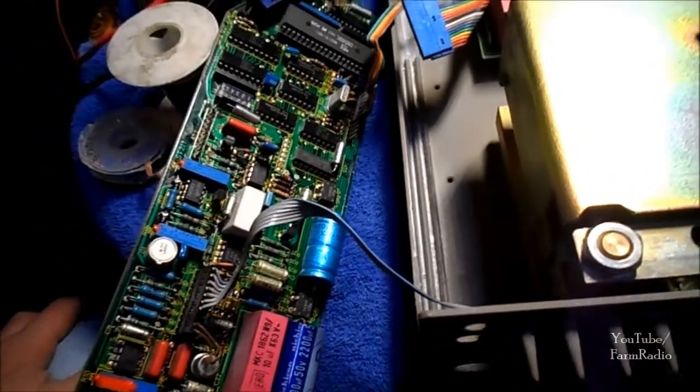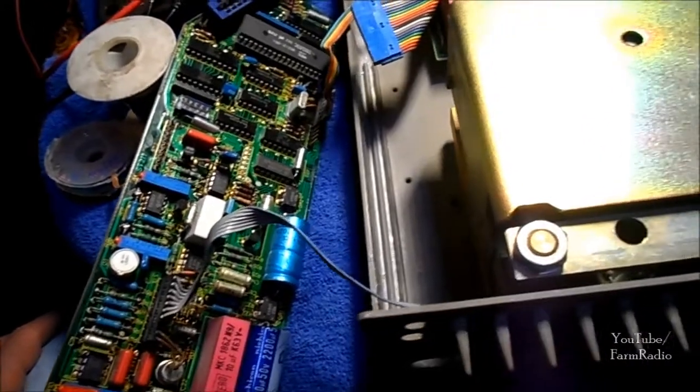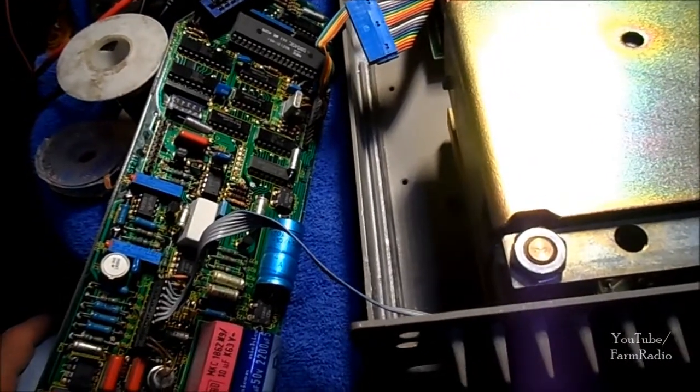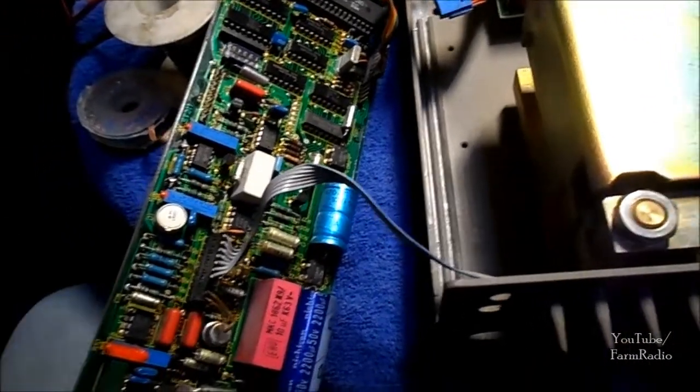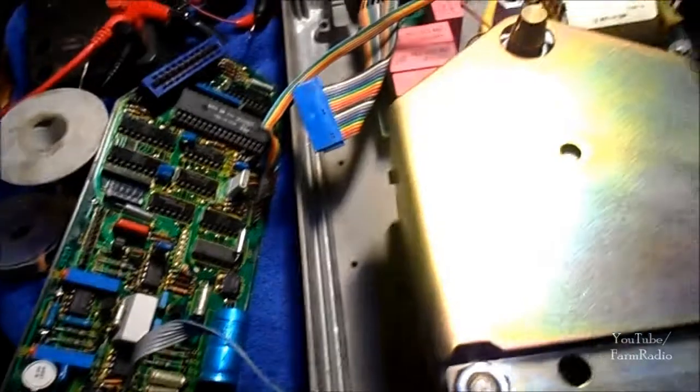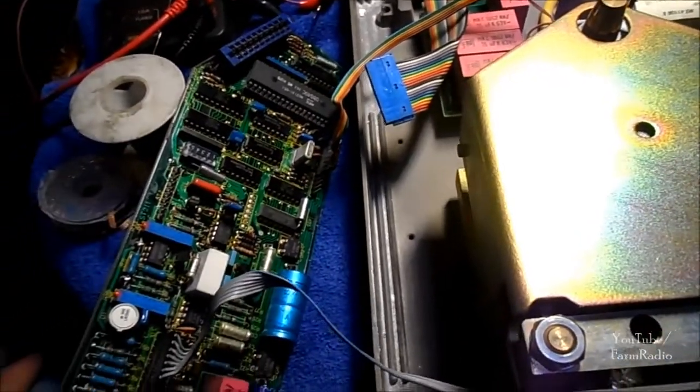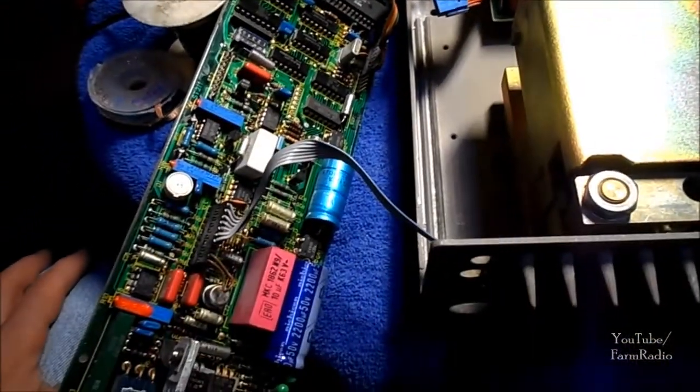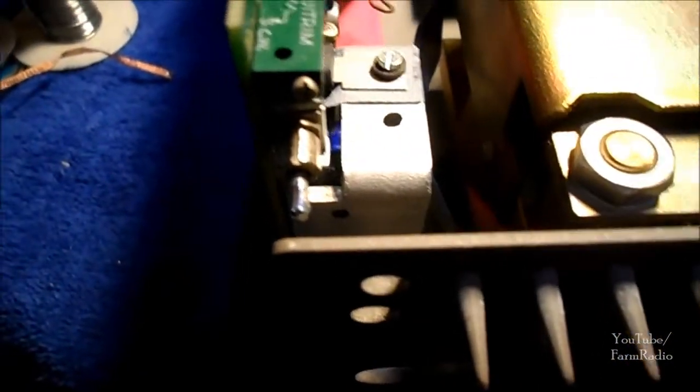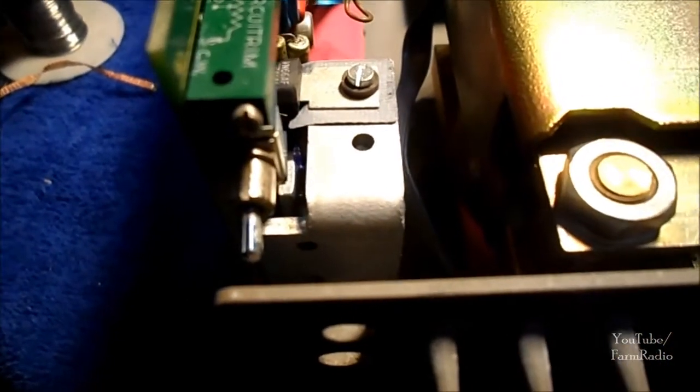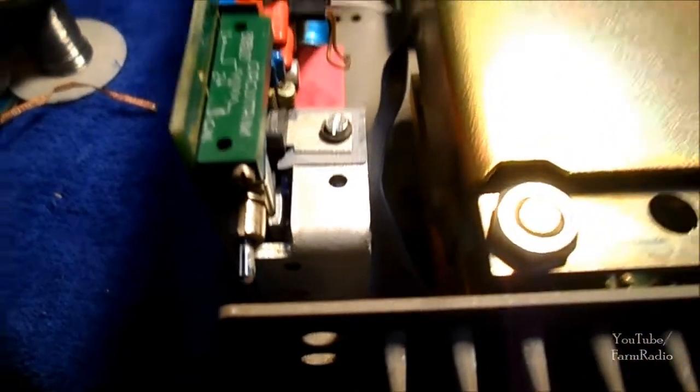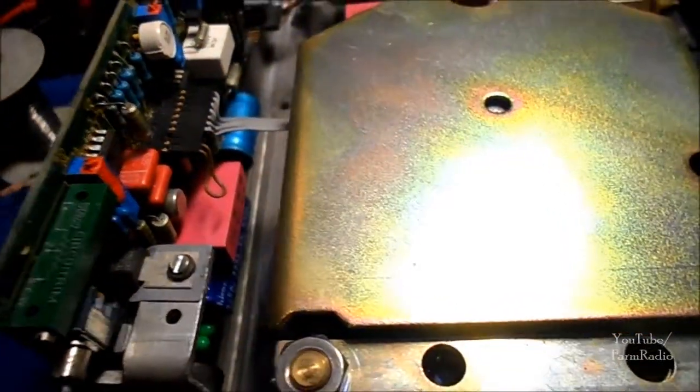I'm in contact constantly with the customer, so we'll put a parts order in and just change that one out if need be. In the meantime though, we're going to run this thing and see how it does. I'm also going to put a dab of heat sink compound on that heat sink there - doesn't appear to be any on there.